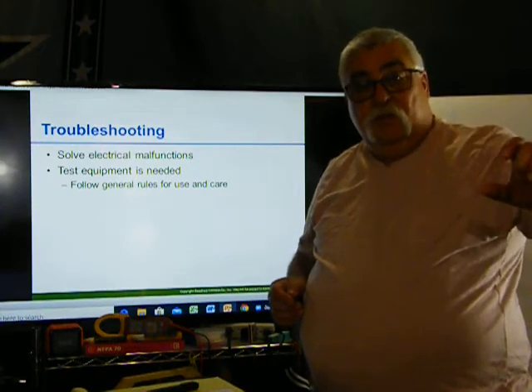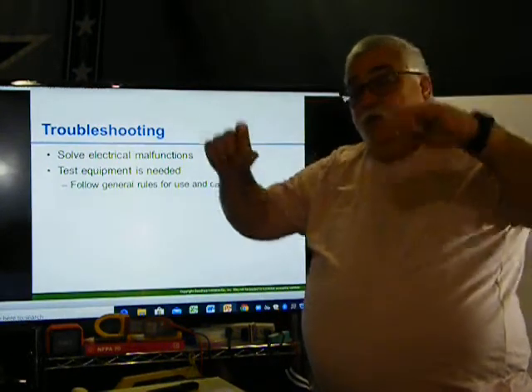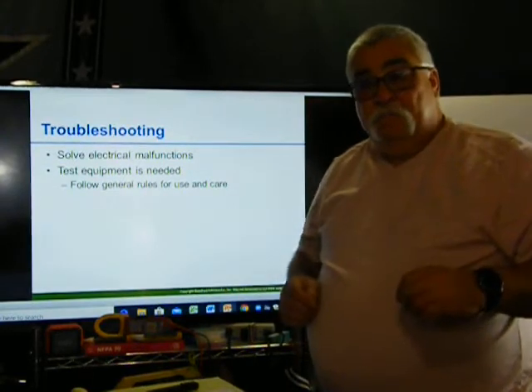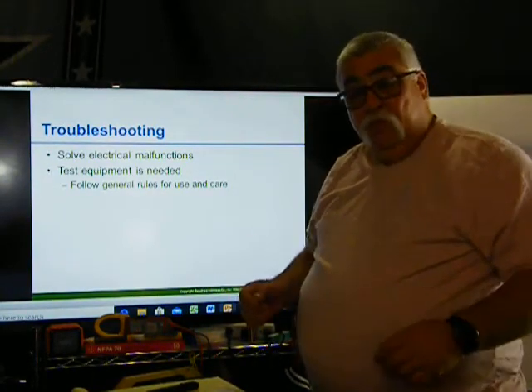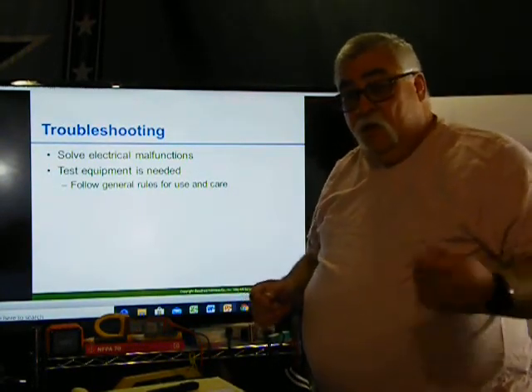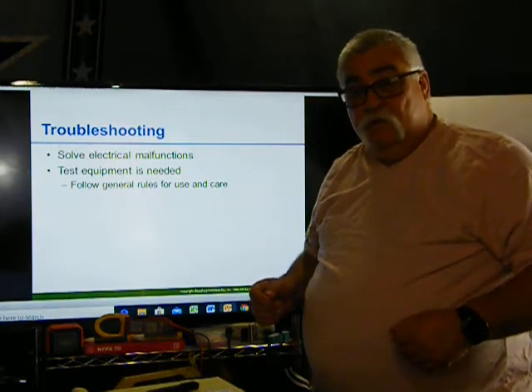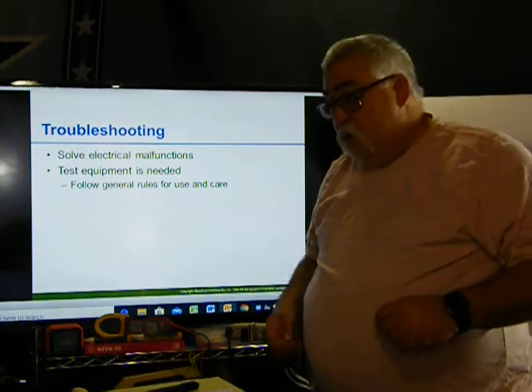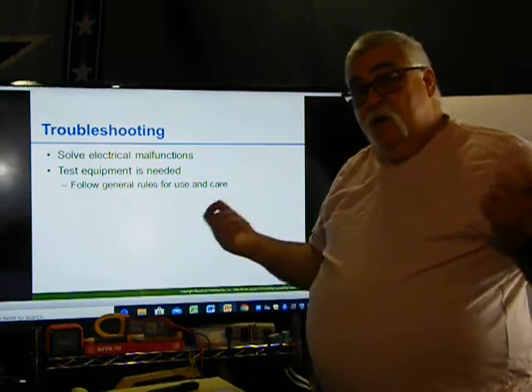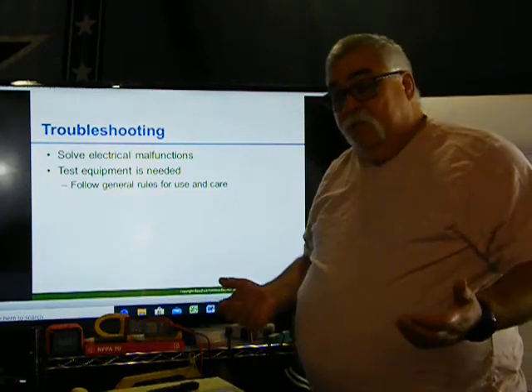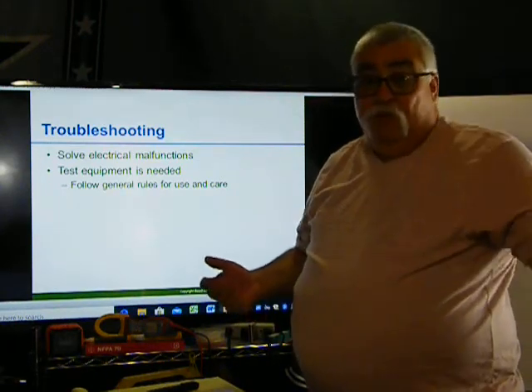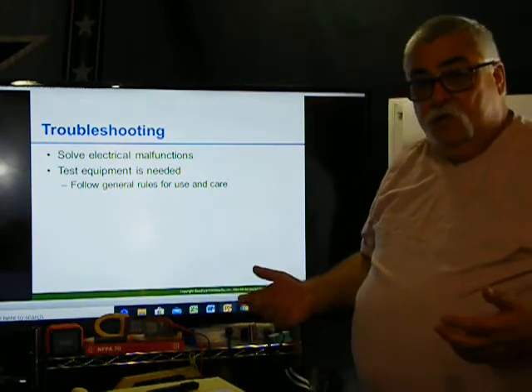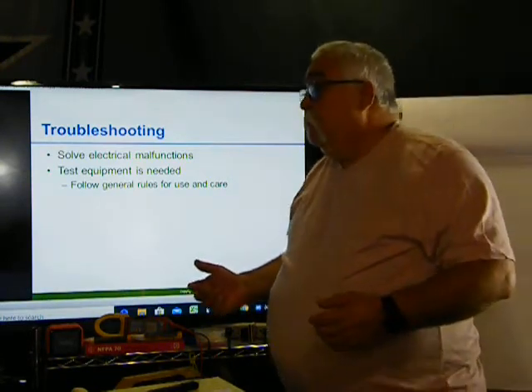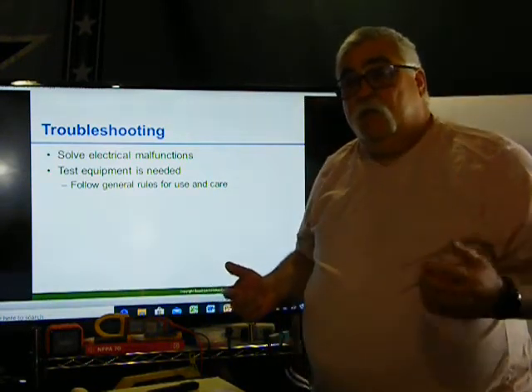And there's only one circuit, and there's a sign that says only use one at a time. But people don't read signs and people don't pay attention. Hey, all I know is I gotta heat up my lunch. So somebody throws something in the toaster oven, somebody throws something in the microwave, power goes out. It's a very simple fix. Breaker trip, overload. There's no short circuit, it was an overload. Okay, so it's simple things like that you can tell.